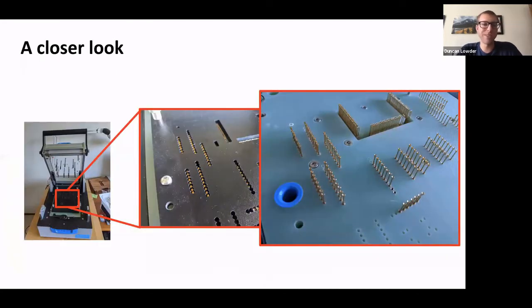Here's a closer look at that same interface cartridge within the fixture. The first image is the complete fixture without a device under test. The middle picture is the moving plate. From here, you can see the test probes are recessed a little bit from the plate, because you don't want the device you're testing to interface with any of the pogo pins or instrumentation before it's closed in the fixture. On the right side, that's what the fixture looks like, where you can see all the pogo pins poking up through their holes, and there's a lot of them.